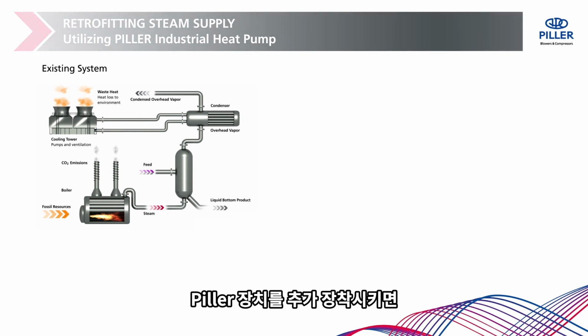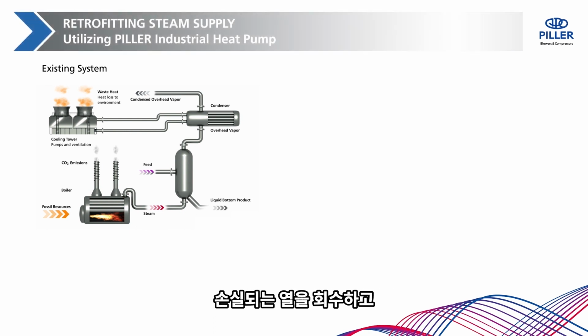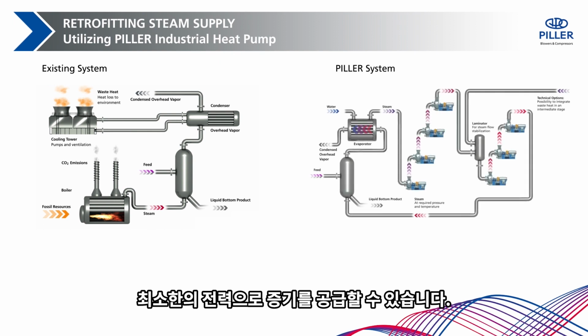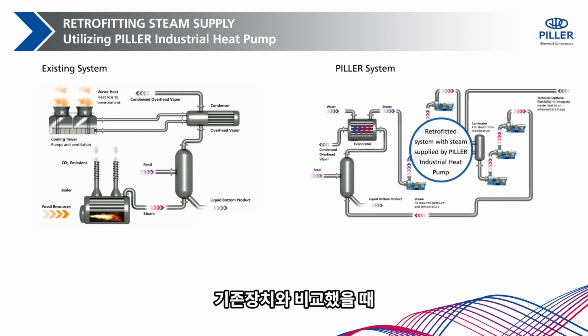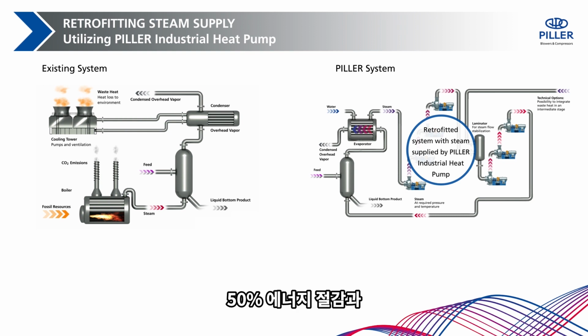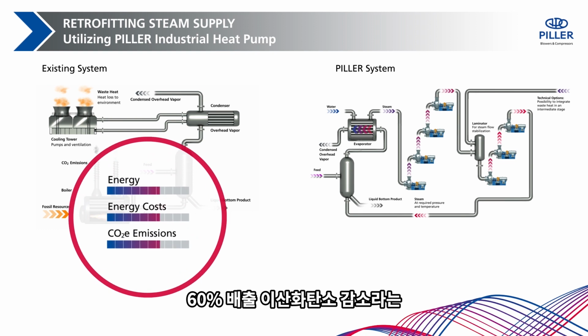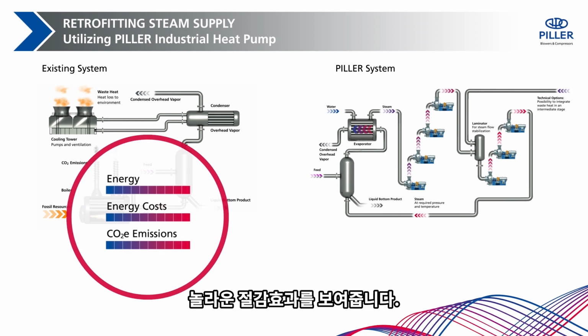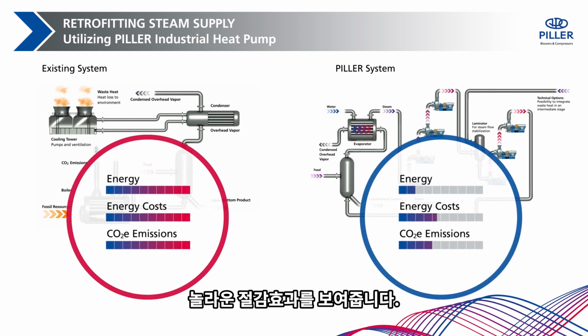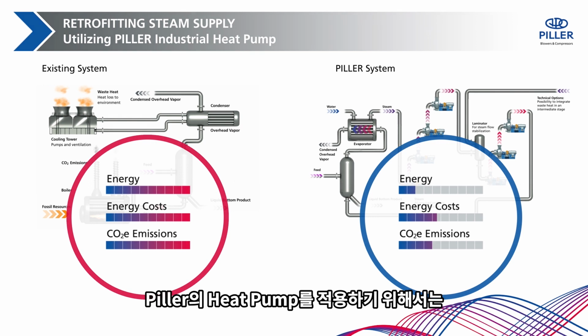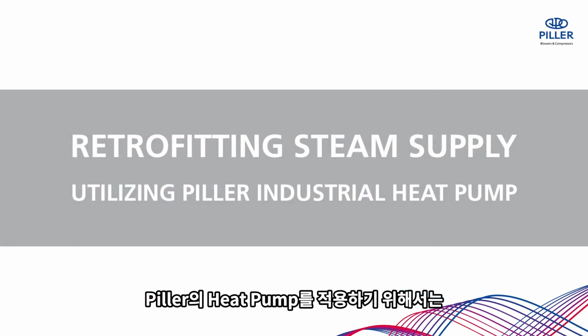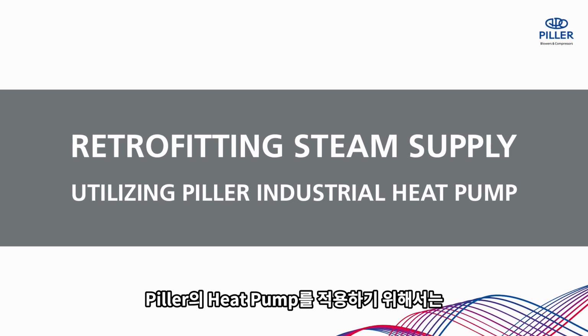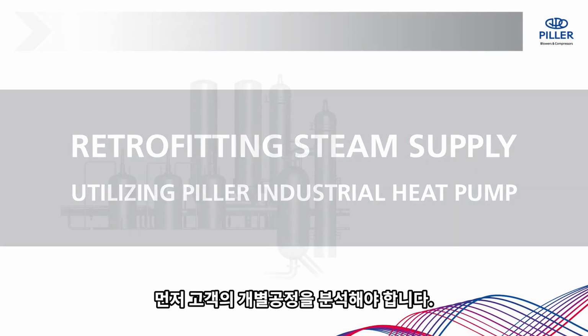The retrofit with the PILLER system recovers waste heat from the process and supplies steam using a minimum of electrical power. The comparison of the existing system to the PILLER system shows the remarkable savings of our solution. Over 50% savings in energy costs and more than 60% reduction of CO2 emissions. The successful conversion to an industrial heat pump made by PILLER starts with the analysis of your individual process.